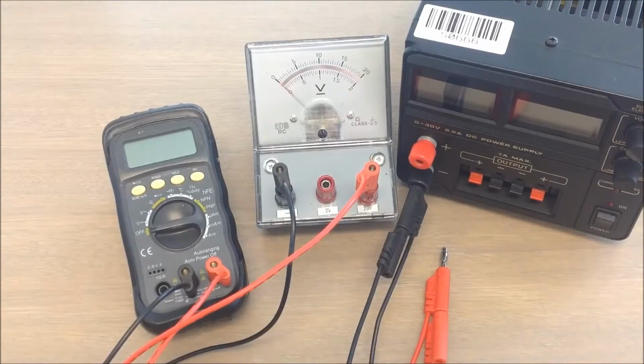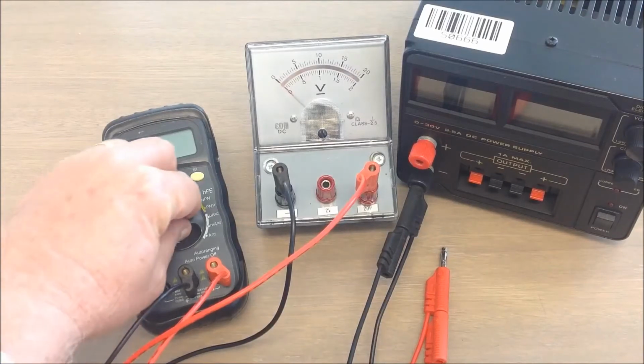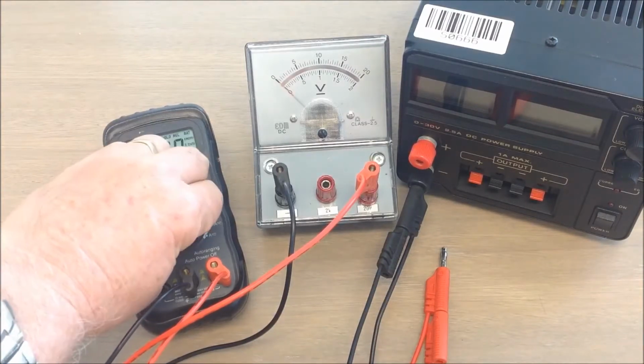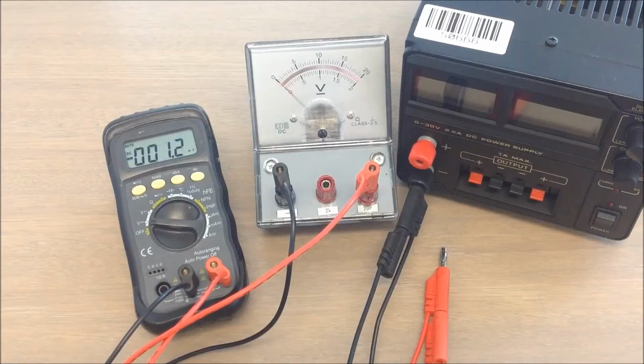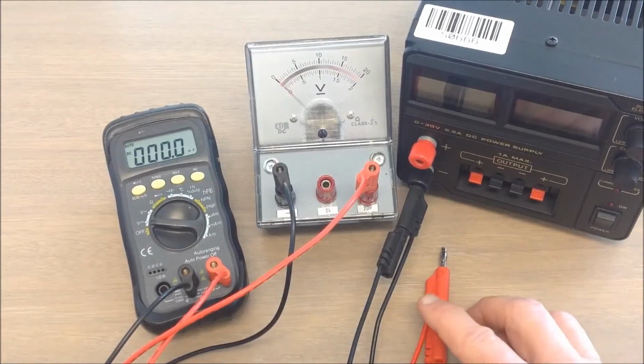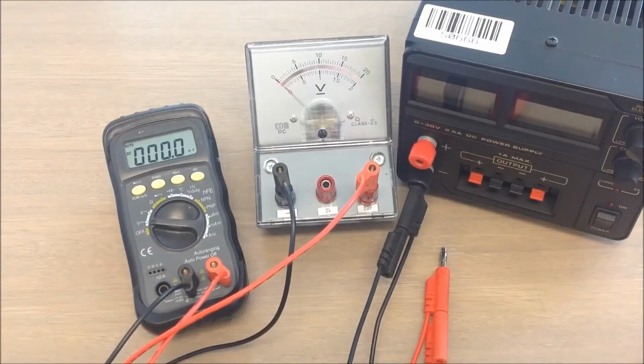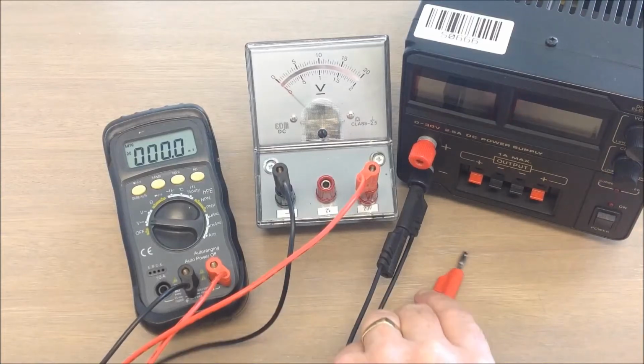In the last part of this exercise, we're going to take you through a procedure called calibration. This is how to use a meter that is not reading correctly and how to make adjustments for that. First, to demonstrate what we mean, here I have a digital multimeter and a moving coil meter. They're wired in parallel, but they're not actually plugged into anything at the moment, and they're both reading 0 volts.